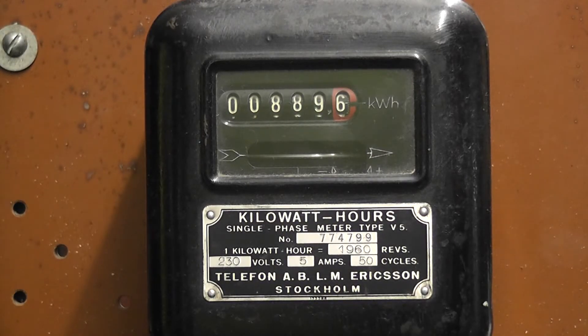Good day viewers. In this video I have an old kilowatt hour meter made by Telefon A.B. L.M. Ericsson in Stockholm, Sweden. This particular meter is rated at 230 volts, 5 ampere. One kilowatt hour is one thousand nine hundred and sixty revolutions — nearly two thousand revs, so that's quite a high speed meter.